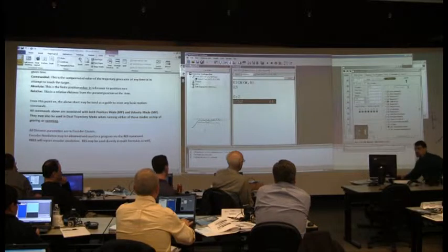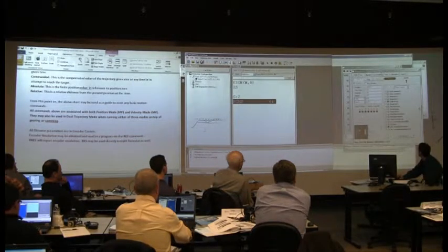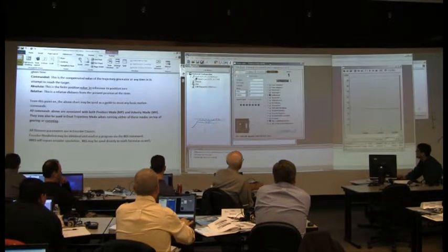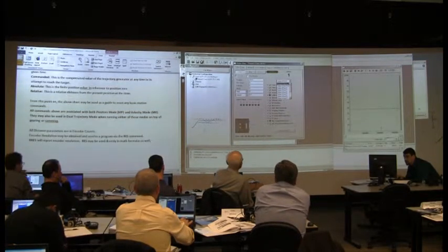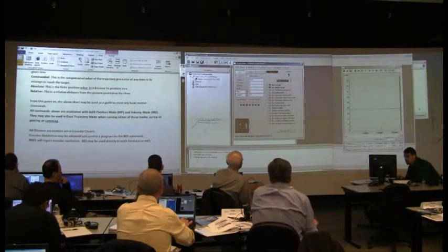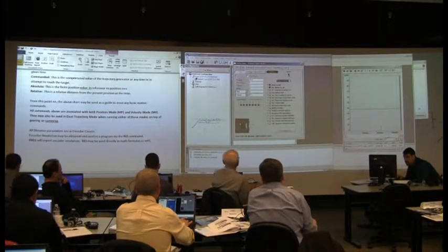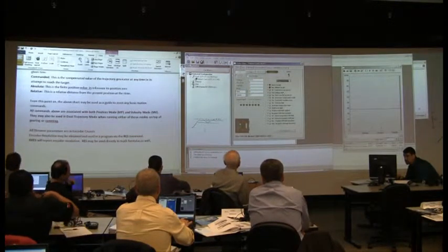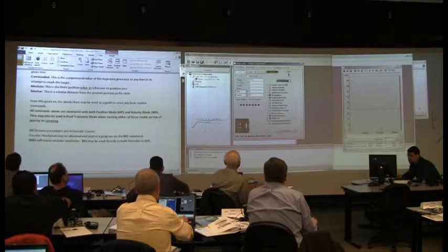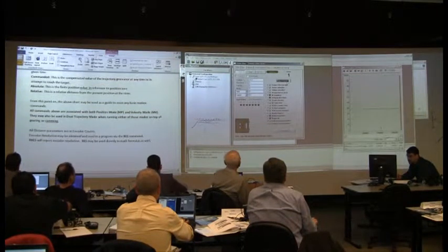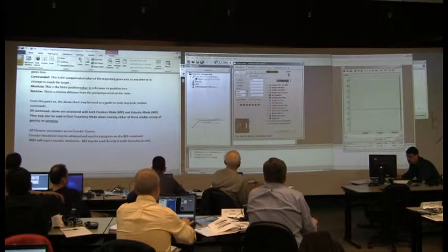Otherwise, hardware, I'm going to go through some stuff to make sure we're all on the same page and you understand the rest of the hardware limits. Okay? Status word 1, 0, let's get back to it. Bus voltage fault, we already talked about high and low bus voltage, but you don't know which one you hit. If you go down in the status words, you'll actually find the high and low bus voltage fault.